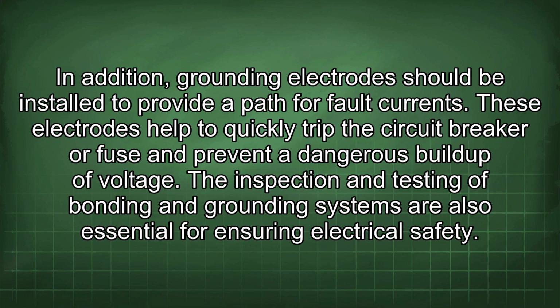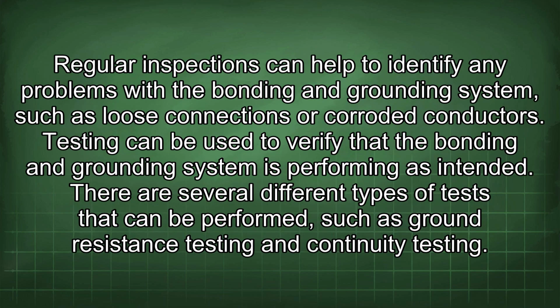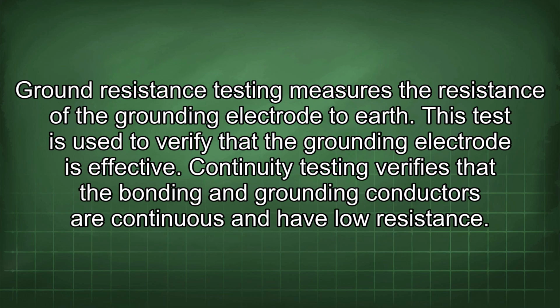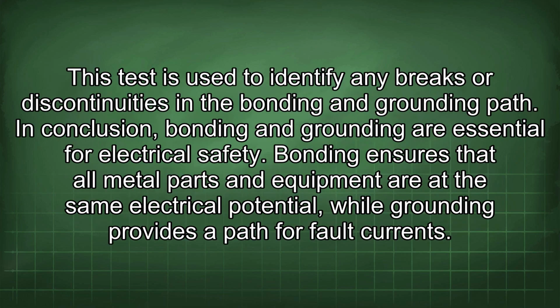The inspection and testing of bonding and grounding systems are also essential for ensuring electrical safety. Regular inspections can help to identify any problems with the bonding and grounding system, such as loose connections or corroded conductors. Testing can be used to verify that the bonding and grounding system is performing as intended. There are several different types of tests that can be performed, such as ground resistance testing and continuity testing. Ground resistance testing measures the resistance of the grounding electrode to earth. This test is used to verify that the grounding electrode is effective. Continuity testing verifies that the bonding and grounding conductors are continuous and have low resistance. This test is used to identify any breaks or discontinuities in the bonding and grounding path.